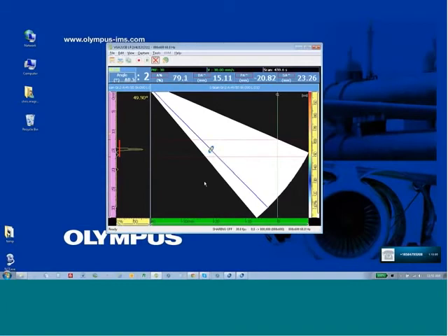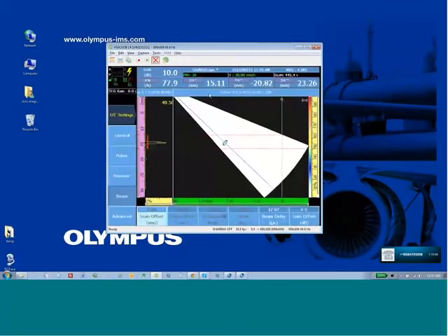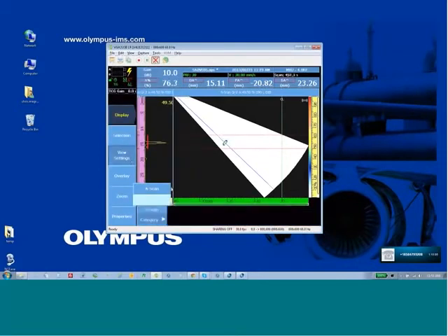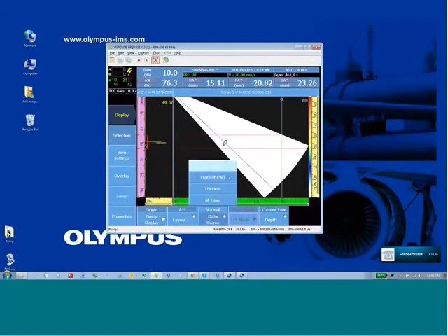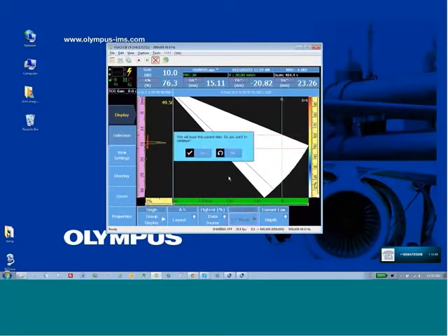quality. Now, prior to any calculation, prior to any calibration, we're coming directly out of the focal law calculator. We can see that the depth of the side drilled hole is correct. If we change under display to view settings, selection, highest amplitude, the software will automatically track the signal in the gate.